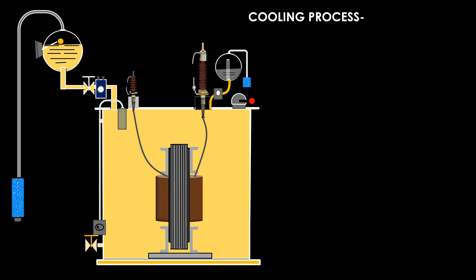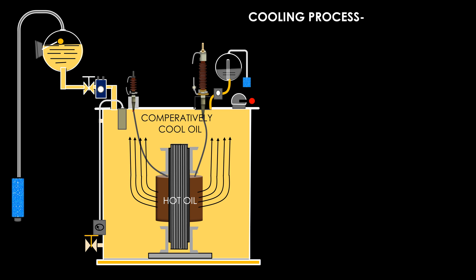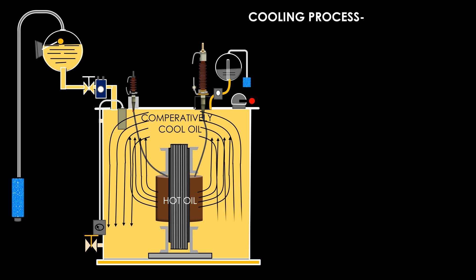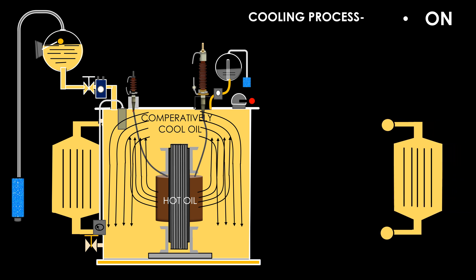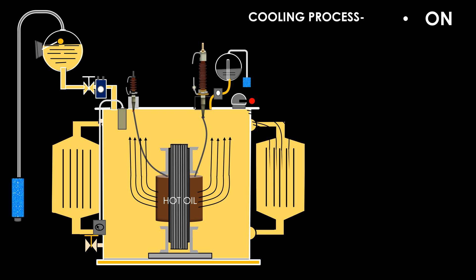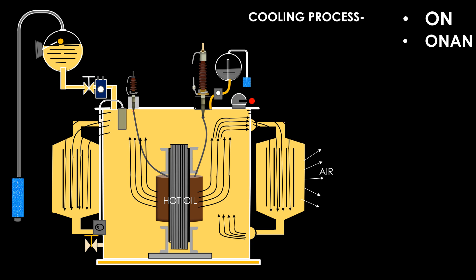During transformation of voltage, hot oil circulates toward the upper part of the tank, losing some heat there to the surrounding air near the tank wall, while relatively cool oil goes downward. As a result, circulation of hot and cold oil occurs naturally. When this natural hot and cold oil circulation occurs, the process is termed oil natural. When a radiator bank is used, circulation of the oil is done through the radiator bank, which is made of groups of thin small tanks or tubes. Some heat is radiated into the air through the cooling tubes or fins — this process is called ONAN: oil natural, air natural.